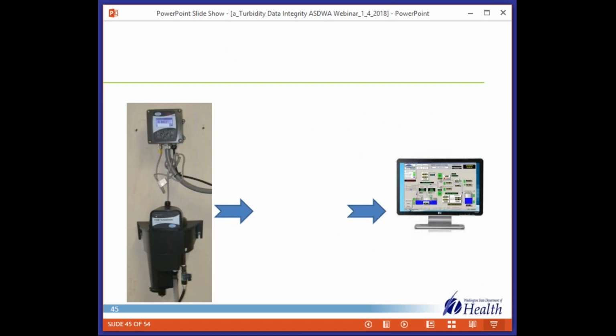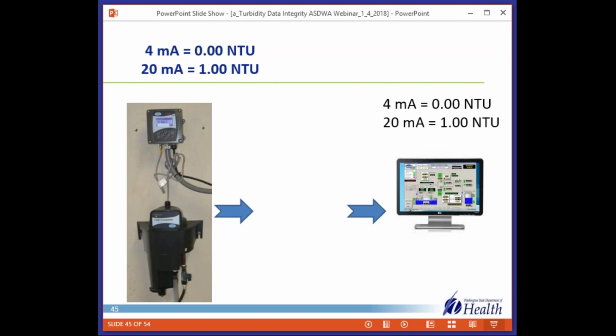So I want to show you just a simple example for how this works so you can get it in your head. This is a finished water turbidimeter, and it's set with a signal span of 0 to 1. We would rather see 0 to 5, but this is how they were when we found them. And the SCADA was also set up that way, so it was matched. So this system had a regulatory violation. It exceeded 0.3 NTU. So this was converted to a milliamp signal, 9.6, which SCADA properly interpreted as 0.35 NTU.